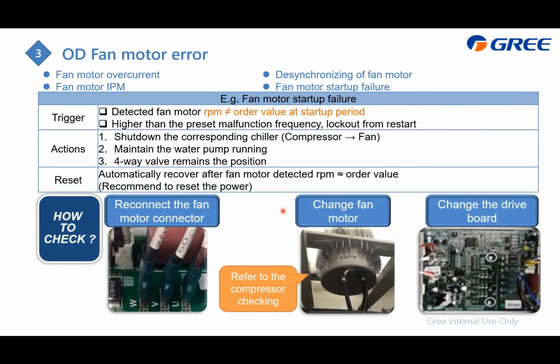And here are the checking measures. First is to reconnect the wiring from the fan motor to the fan motor drive. And the next is just to replace the fan motor. It is not that complicated compared with the compressor. And the last one is that maybe something is wrong with this fan motor drive, so just replace it.